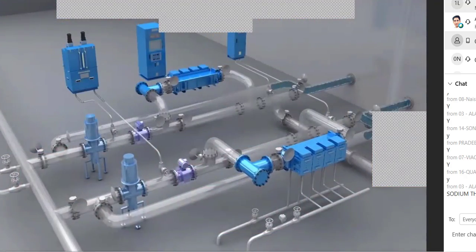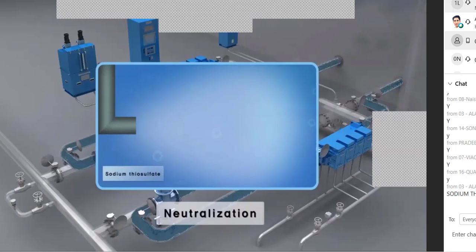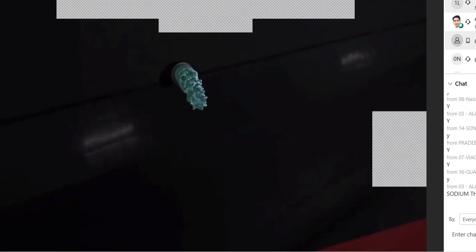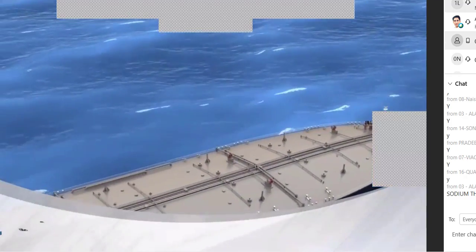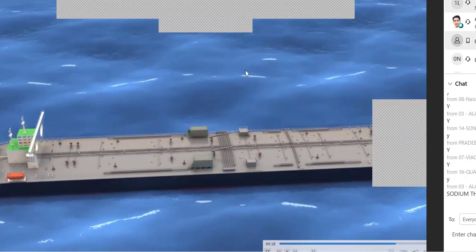ECS does not need to re-treat during deballasting. Before discharging the treated ballast water from the ballast tank, TCU examines the TRO concentration. ANU doses sodium thiosulfate to reduce TRO value down to 0.1 ppm before discharge. The neutralized water no more needs to treat. TechCross provides various installation solutions for each project, needs of the shipyards and the ship owners. This is one of the general installation references on tanker. If there is no pump room but submerged ballast pump, you can make safety room on deck.